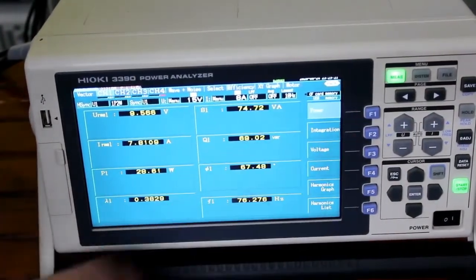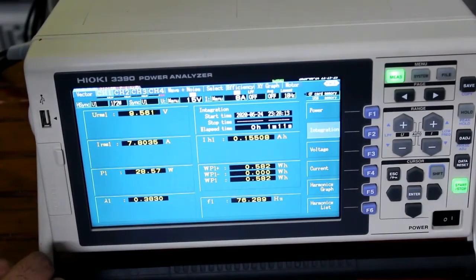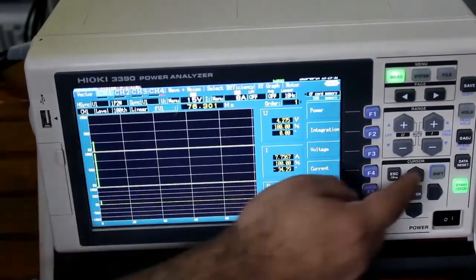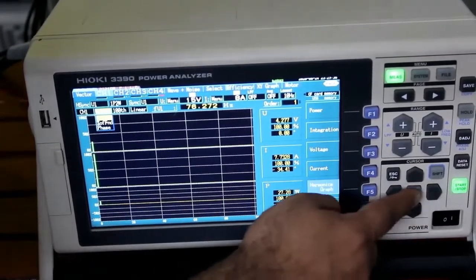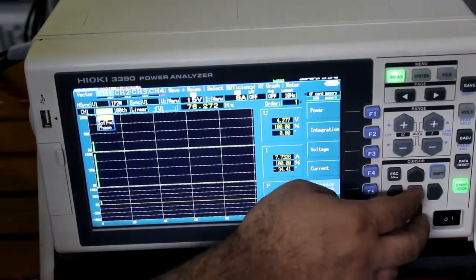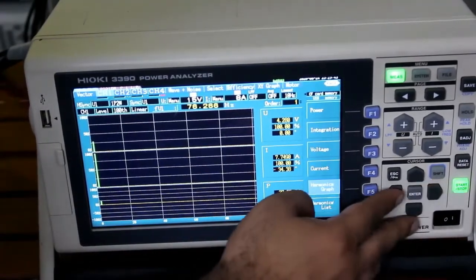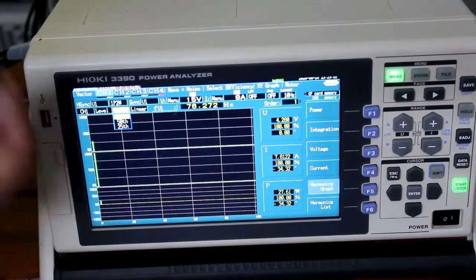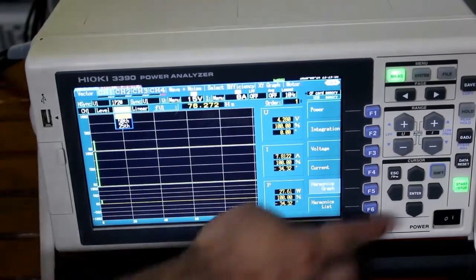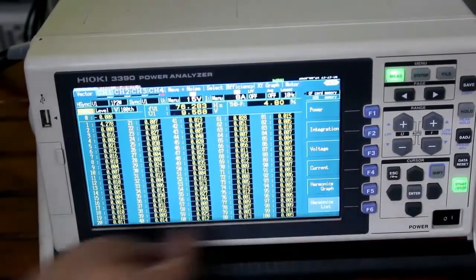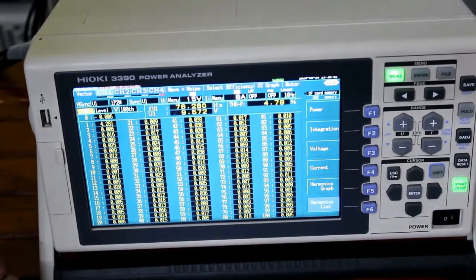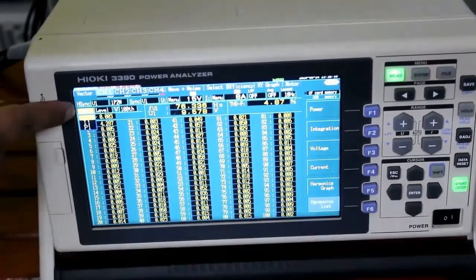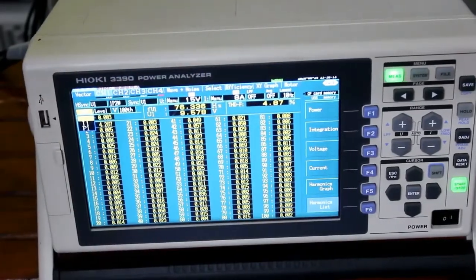Phase one parameters include power, integration, voltage, current, harmonic graph, and harmonic list. The harmonic graph is shown phase-wise and you can select phases, view percentage of fundamental, and the instrument can show up to 100th order harmonics. You can select whether to calculate up to 50th or 25th order. The harmonic list is also viewable. Basic THD is shown for each phase — related to voltage, current, and power — and harmonics can be seen for all four phases.